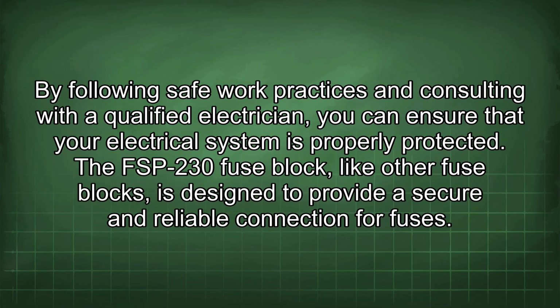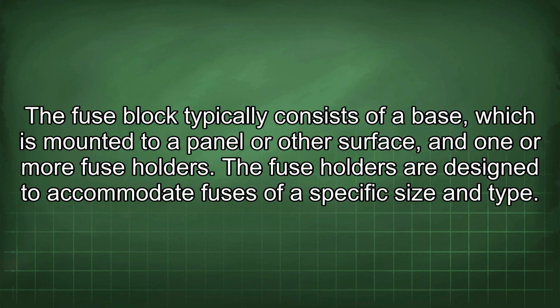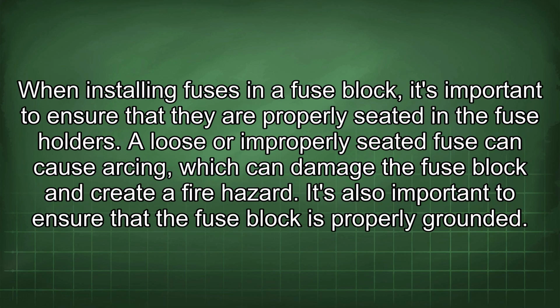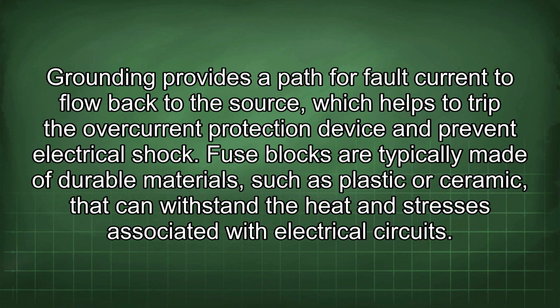The FSP-230 fuse block, like other fuse blocks, is designed to provide a secure and reliable connection for fuses. The fuse block typically consists of a base, which is mounted to a panel or other surface, and one or more fuse holders. The fuse holders are designed to accommodate fuses of a specific size and type. When installing fuses in a fuse block, it's important to ensure that they are properly seated in the fuse holders. A loose or improperly seated fuse can cause arcing, which can damage the fuse block and create a fire hazard. It's also important to ensure that the fuse block is properly grounded. Grounding provides a path for fault current to flow back to the source, which helps to trip the overcurrent protection device and prevent electrical shock.